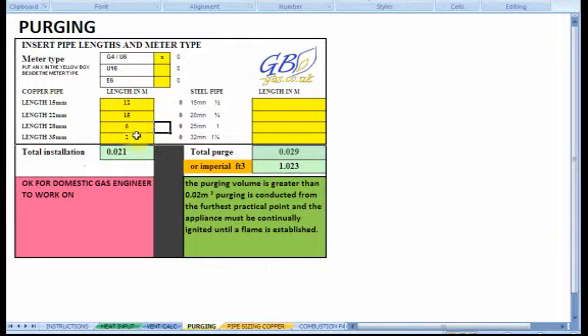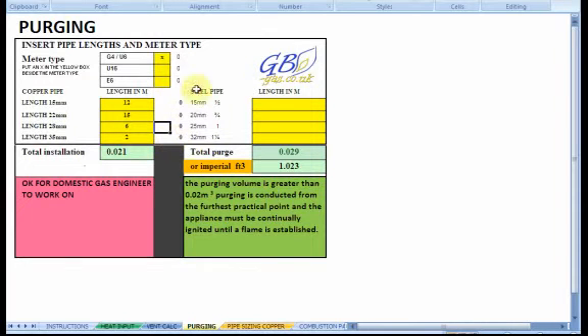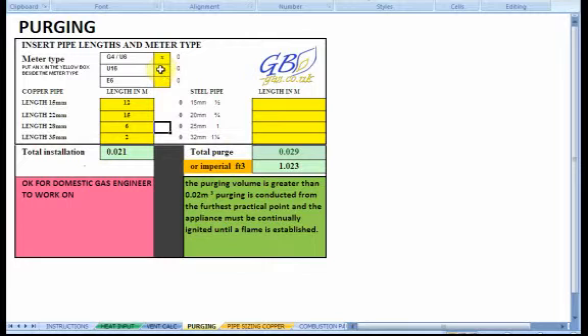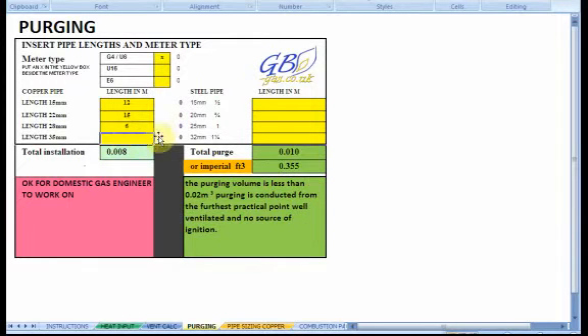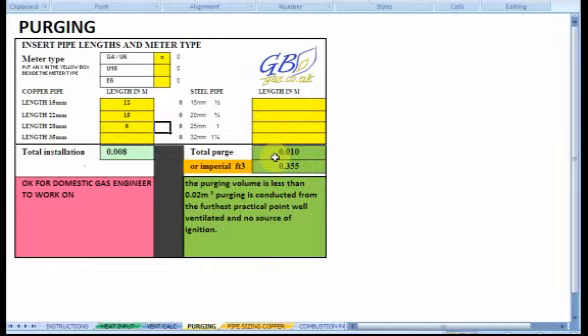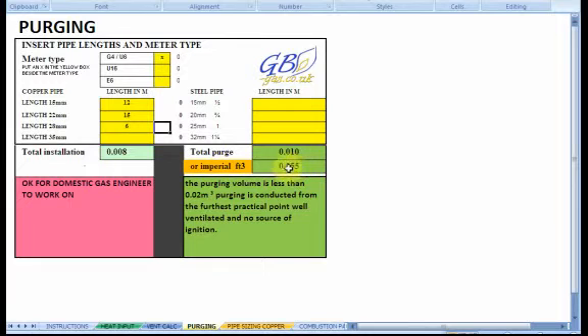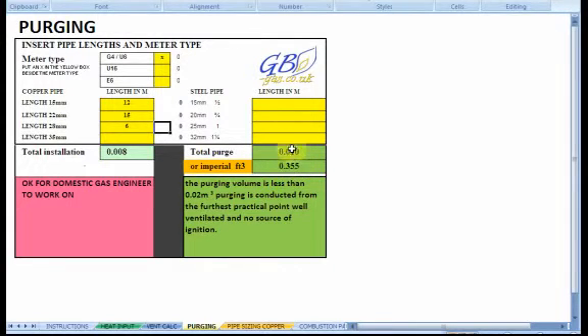Once we start getting into pipes that are bigger than 28 millimetres, such as the 35 mil pipe, and metres that are bigger than the G4 or the E6, we've got a U16 in there, then it will start to work out a purge volume. If I take that length for the 35 out, you will see that it goes back to the normal purge volumes. And for a metric metre, it's always 0.010 metres cubed. And for an imperial metre, it's 0.355 of a cubic foot.